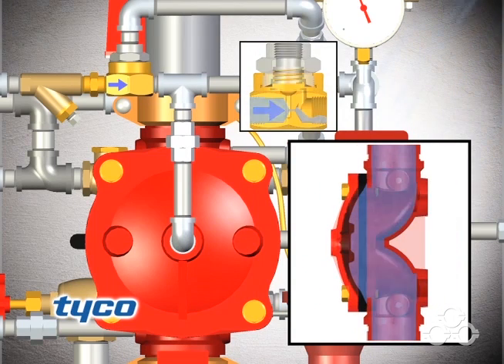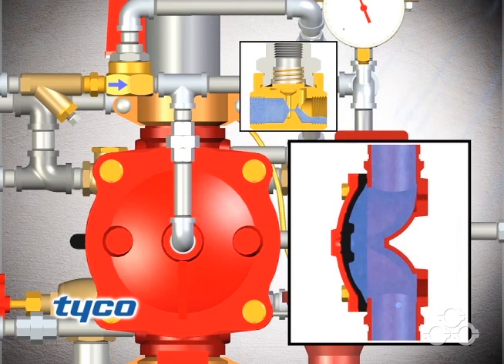As water flows into the system, the automatic shut-off valve pilot chamber becomes pressurized and shuts off the diaphragm chamber supply, preventing the DV-5 diaphragm chamber from becoming re-pressurized and thereby preventing the DV-5 waterway from closing during a fire.